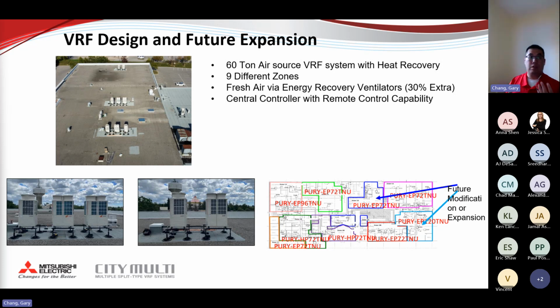And on top of that, there used to be a QA, some sort of manufacturing, back in the old days before my time. So we are really able to switch from a 90-ton to 60-ton. And on top of that, for any rooftop unit that was built 30 plus years ago, 30 years later, it is not performing at its peak performance. So we have a couple of different opinions, then we are okay with 60-ton. And then even last week throughout the heat wave, or last year throughout the heat wave, people are fairly comfortable with the 60-ton air source unit.